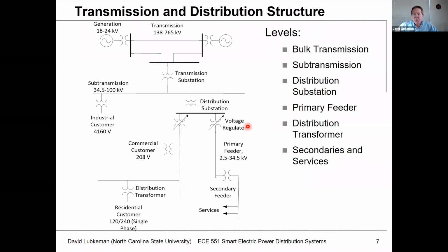This is why distribution engineering can be a class separate from the transmission class, 550. Because if we regulate the voltage at the top of all these medium voltage circuits, I can analyze the circuit separately, keeping that top voltage fixed. It's a design decision made to allow controlling distribution voltage without worrying about how transmission voltage varies.